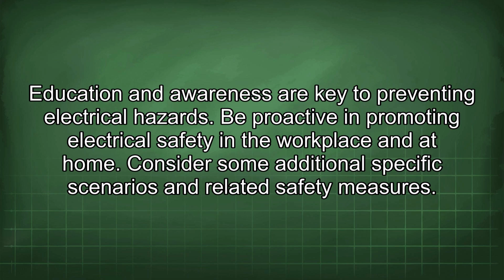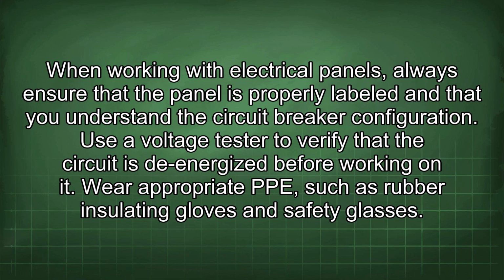Consider some additional specific scenarios and related safety measures. When working with electrical panels, always ensure that the panel is properly labeled and that you understand the circuit breaker configuration. Use a voltage tester to verify that the circuit is de-energized before working on it. Wear appropriate PPE such as rubber insulating gloves and safety glasses.